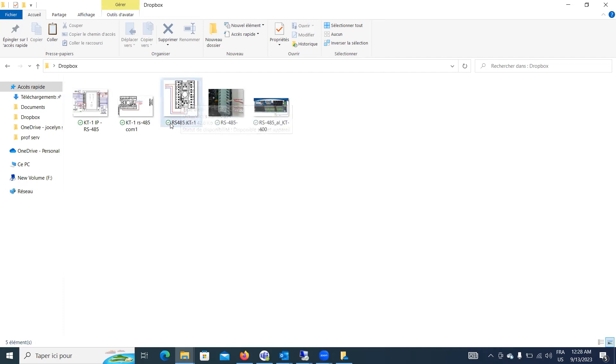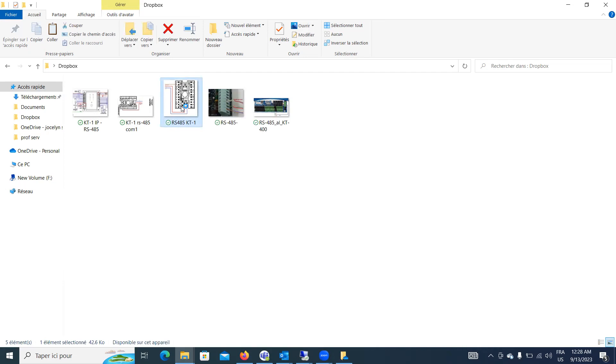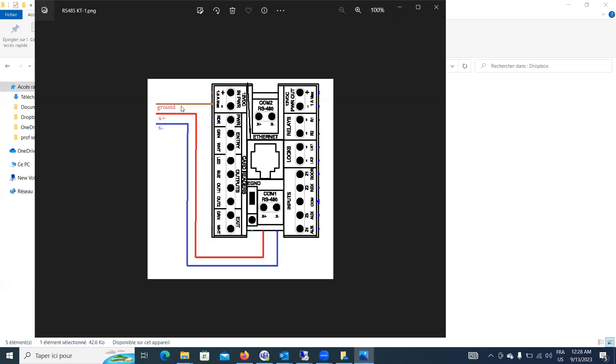Let's say, since we have a KT1, we'll go with a KT1. Okay, so remember we need X plus, X minus. If the entire connection is with KT1, KT2, KT8, if we have those controllers, we can just go with two cables, X plus, X minus, because all of those controllers, they are DC powered.